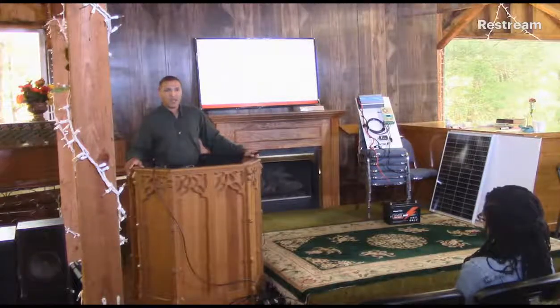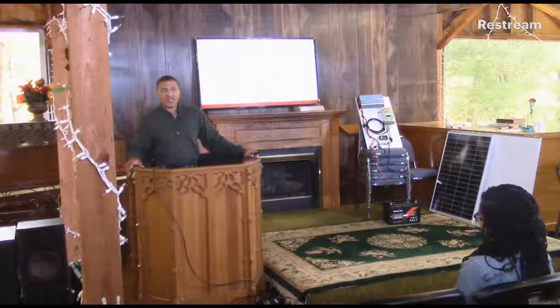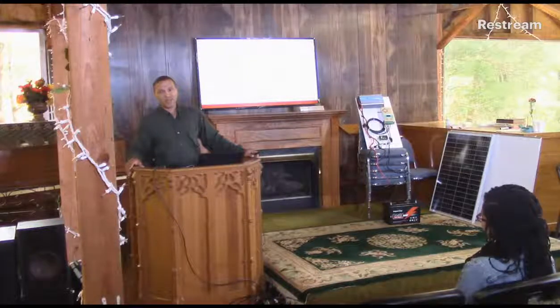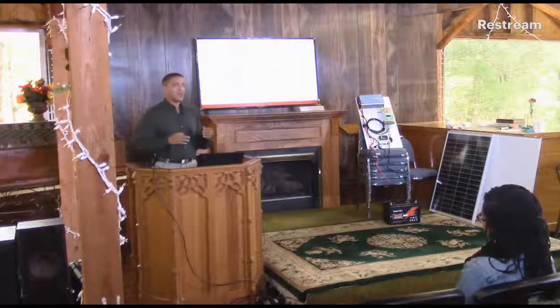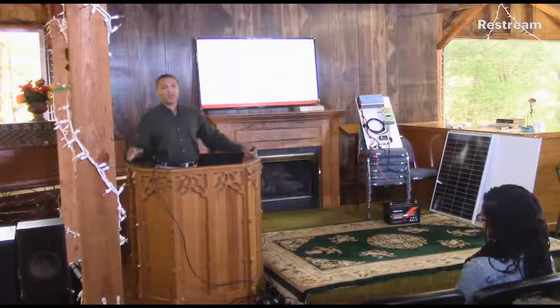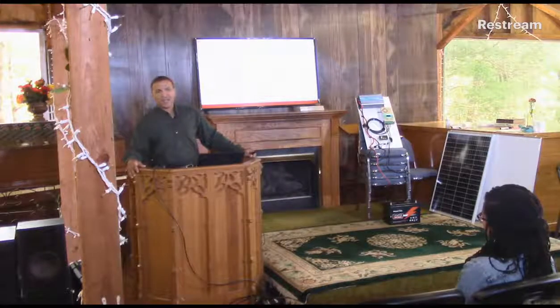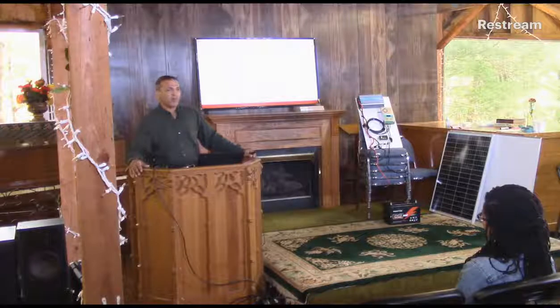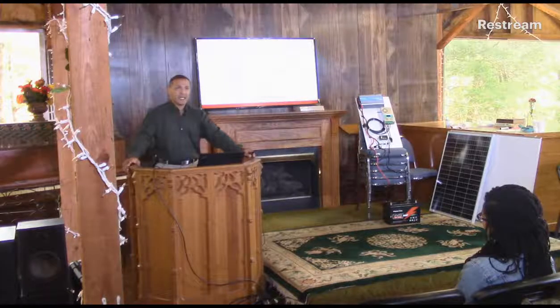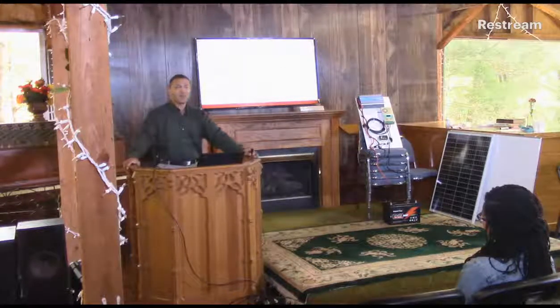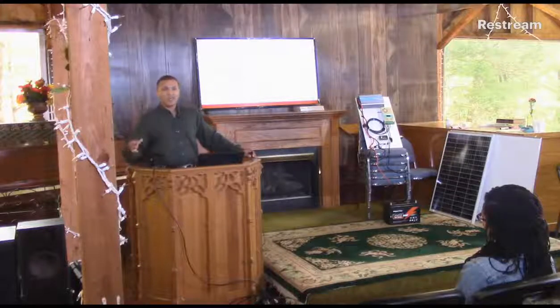30 amps is about all you can push through a 10 gauge wire. Any more than that, you're going to compromise that wire. That wire is going to start heating up and burning, and yeah, you want to be careful. So you have to think about those things when you're doing it. But that wire becomes a heating element. Exactly. Because there's more resistance going through that wire, it's not going to be as efficient.